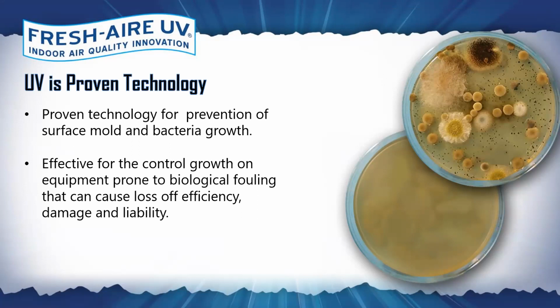The majority of the surface area, which we don't see, which is like an iceberg below the waterline, is what's growing and what's typically foul. So I ask permission, would you mind if we take 2 discs and we do a surface test? Now, what's nice about these contact plates is that the gelatin is bowed. So I'm able to take the gelatin, the disc, and press it into the coil. The fins of the coil slice into the gelatin, and I cap both discs. I give one to the facility director, and I take one back with me.